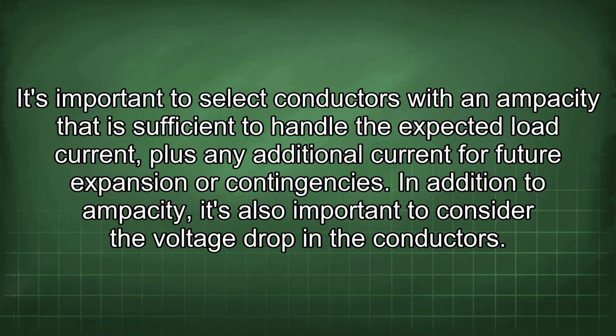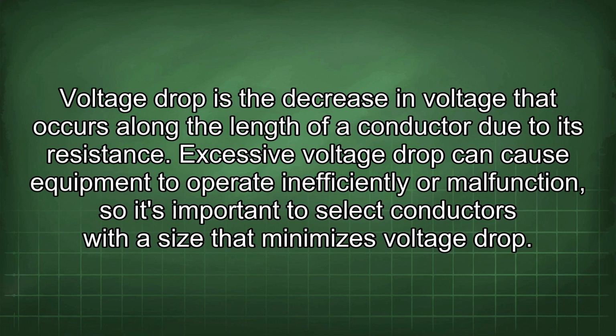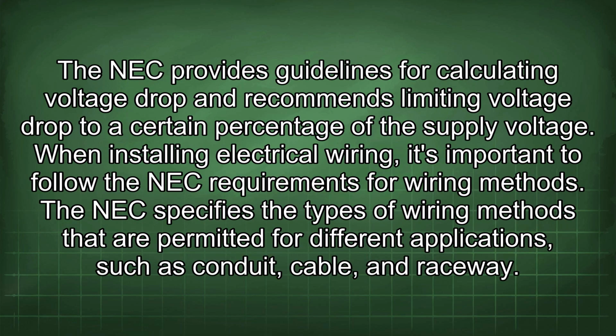In addition to ampacity, it's also important to consider the voltage drop in the conductors. Voltage drop is the decrease in voltage that occurs along the length of a conductor due to its resistance. Excessive voltage drop can cause equipment to operate inefficiently or malfunction, so it's important to select conductors with a size that minimizes voltage drop. The NEC provides guidelines for calculating voltage drop and recommends limiting voltage drop to a certain percentage of the supply voltage.